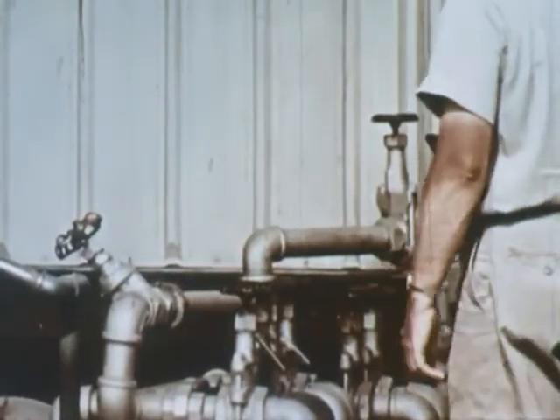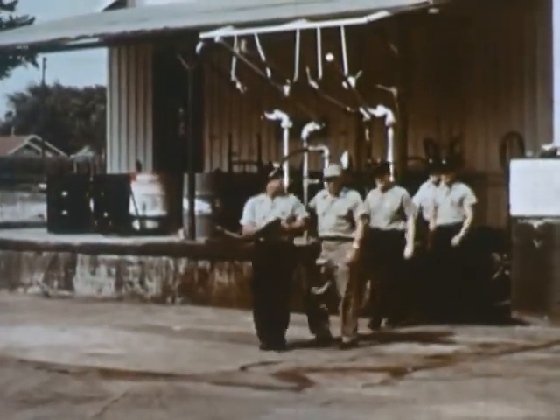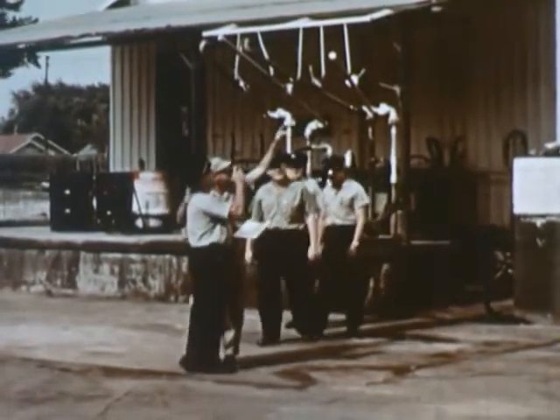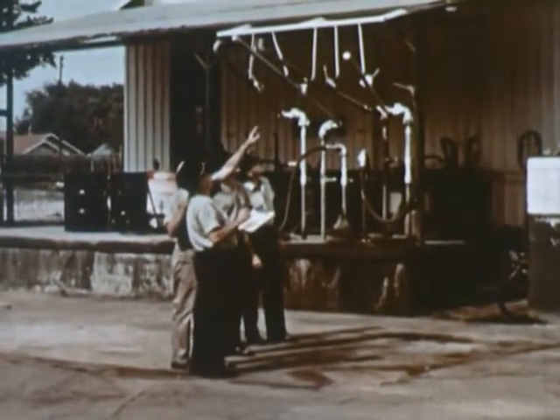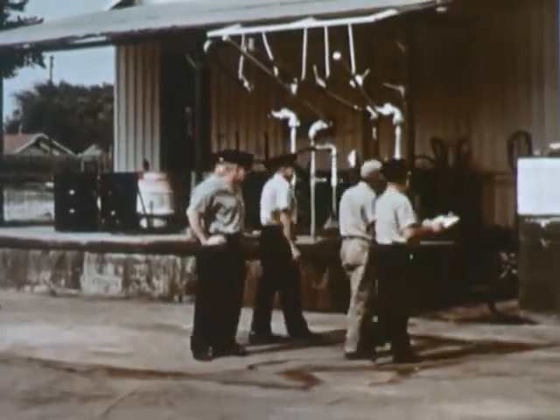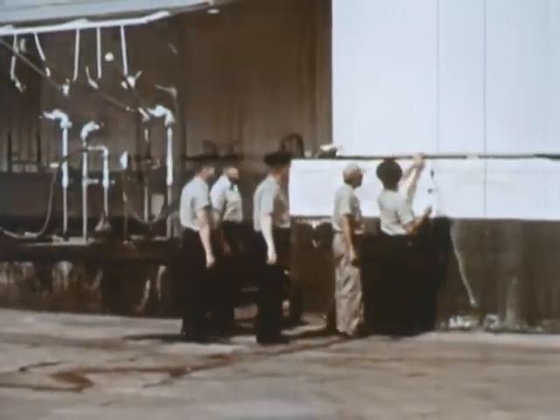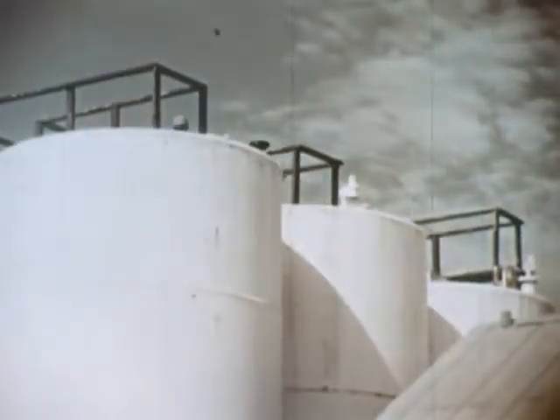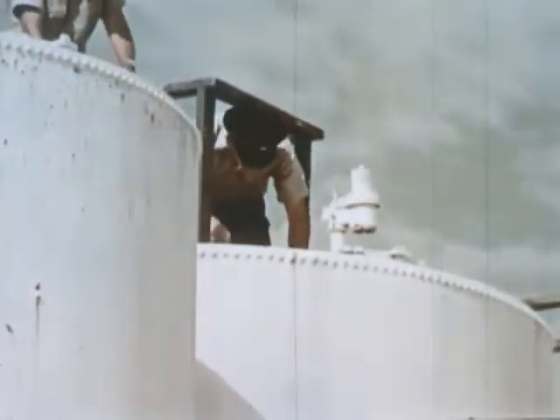The greatest protection for firefighters is the design features for the emergency venting of tanks subjected to fire. The roofs of many vertical tanks are designed to tear loose from the shell before the bottom-to-shell joint fails, and thus serve as an emergency relief to prevent failure at the bottom, which would release the liquid. Therefore, it is important not only to study the bottom joint, but also to compare this with the roof-to-shell joint. However, for vertical tanks not designed with this weakened joint, as in this case, another means must be provided to relieve the pressures developed under fire conditions.